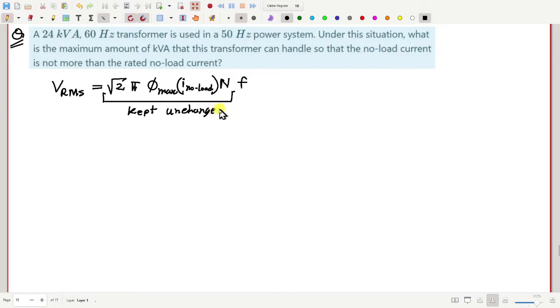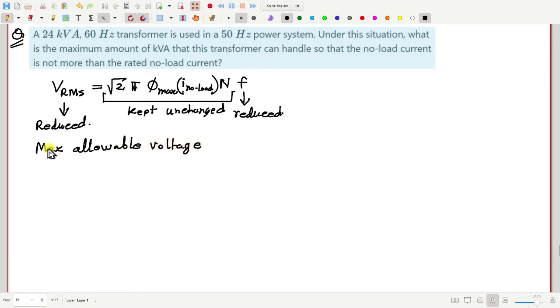But this frequency is reduced by a factor of 5 by 6, that is 50 by 60. Therefore, we cannot apply full rated voltage. We also have to reduce the maximum applicable voltage by the same factor as the frequency. So the maximum allowable voltage, or the new voltage rating, becomes 50 by 60 times the original voltage rating.